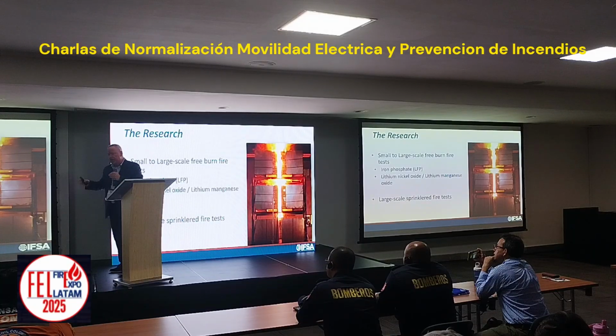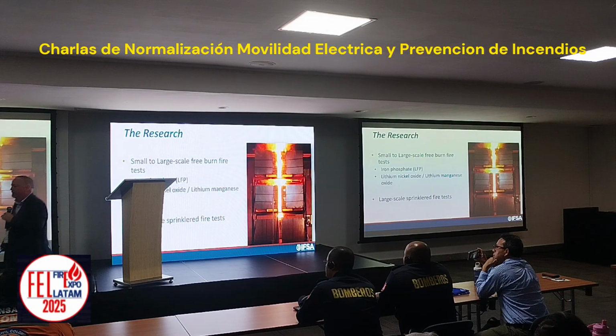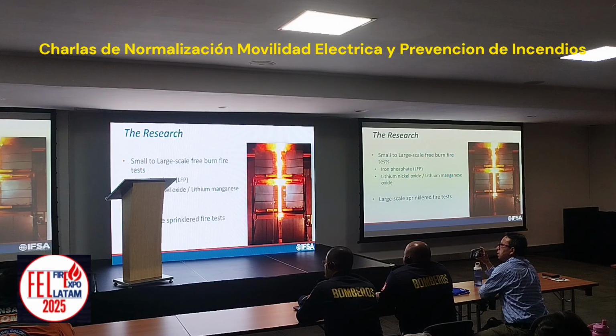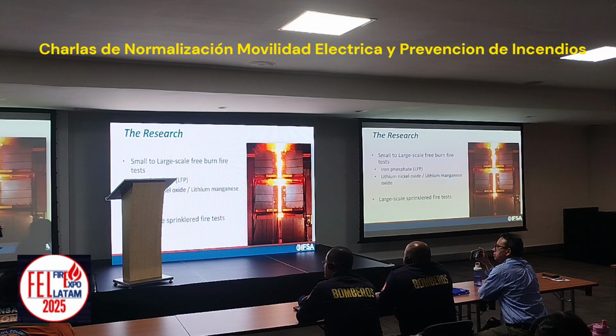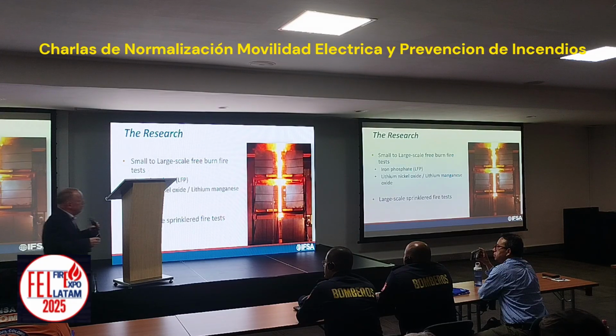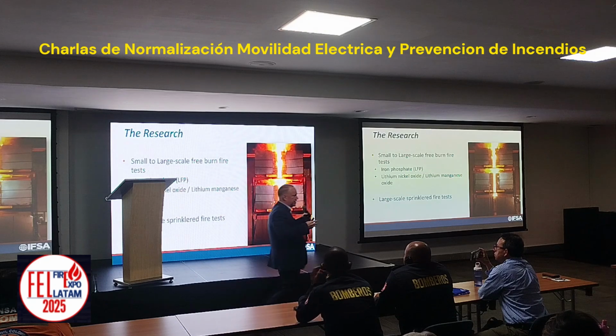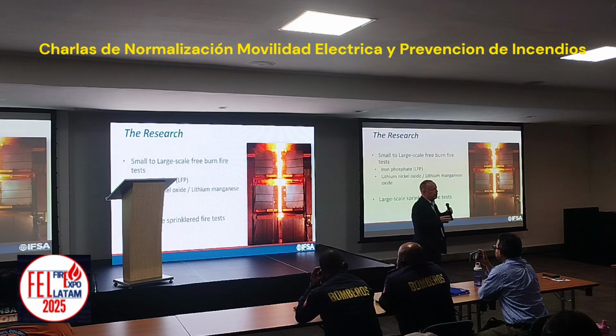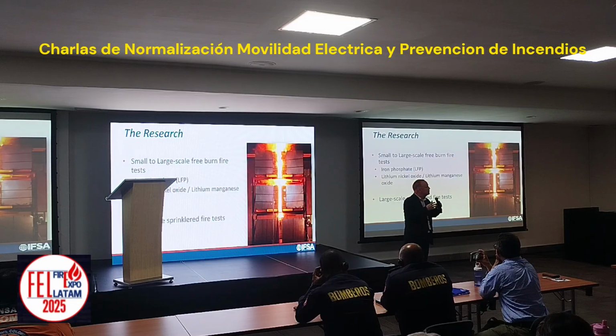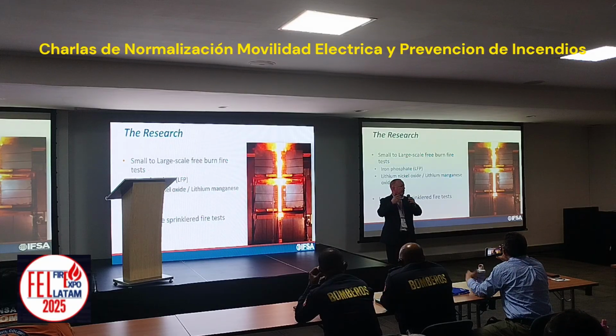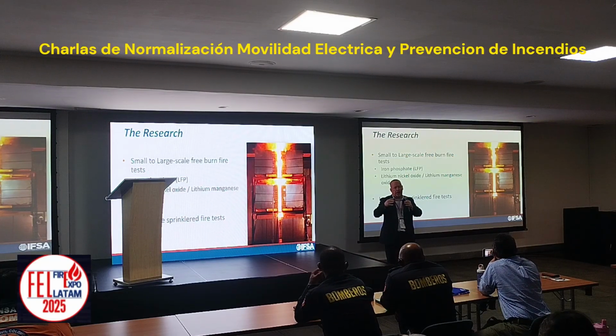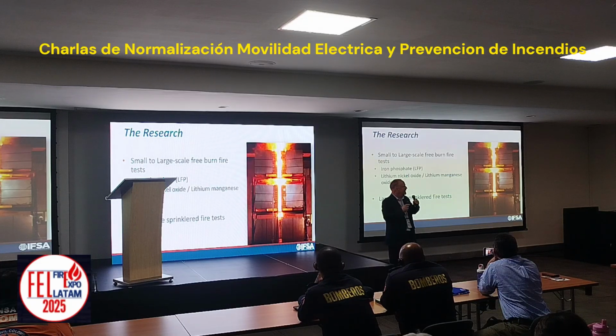Now, there's been considerable research done so far on this particular problem, both large-scale and small-scale sprinkler testing. And what we're basically finding out is it's a combination that has to occur between sprinkler design and some level of containment, to make sure that when the units are exploding, when the units are off-gassing, that they don't spread beyond a specific area.